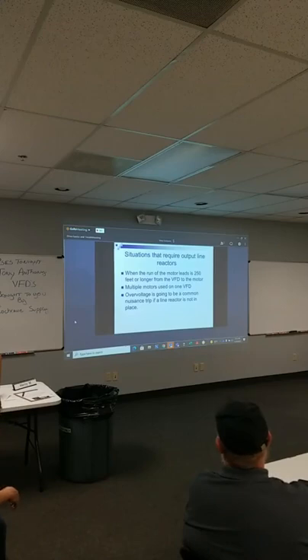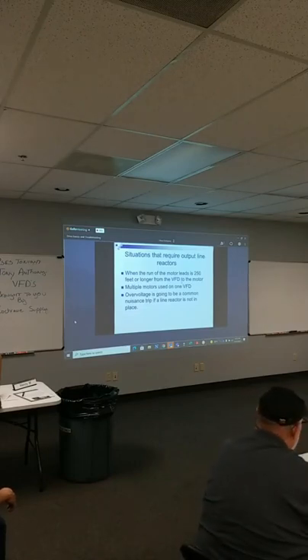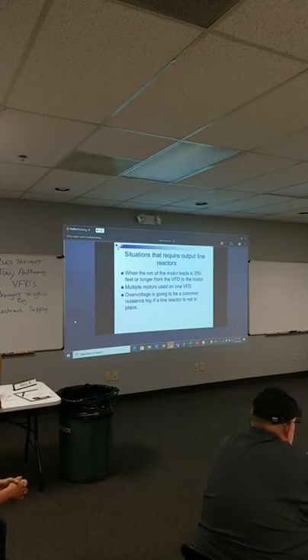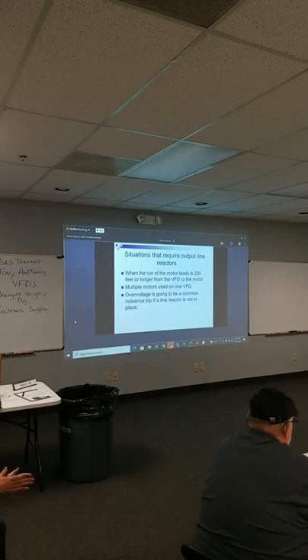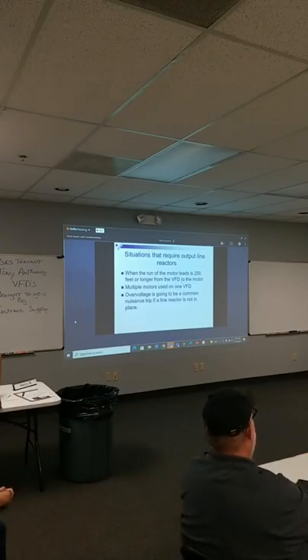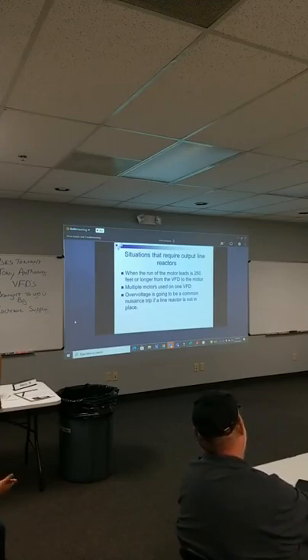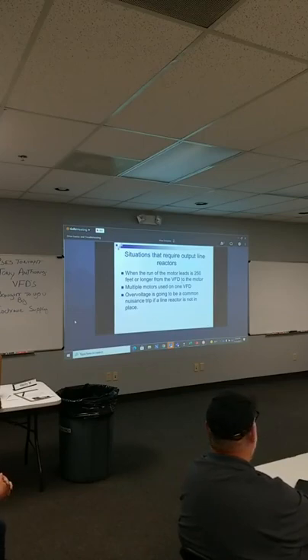Of the motor, is it safe to say the shorter the distance, the better? The less that DC spike's going to be, the longer the motor's going to last, right? So regardless of which motor you use, is it safe to say that the shorter the distance, the better, because that will reduce that DC voltage spike at the motor, therefore allowing the motor to probably last longer? Yes. The shorter the lead run, the less that voltage is going to build up. So yeah, you don't need it. That's why the rule of thumb usually, especially with the premium efficiency motors we have today, is anything under a couple hundred foot, you most likely are okay. And the drive provides overload protection for the motor, so we're good there.